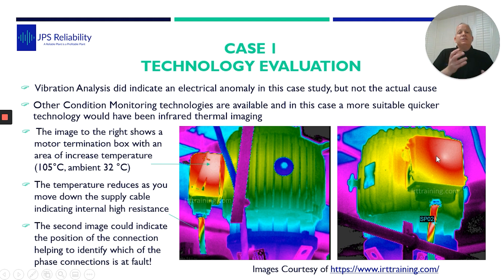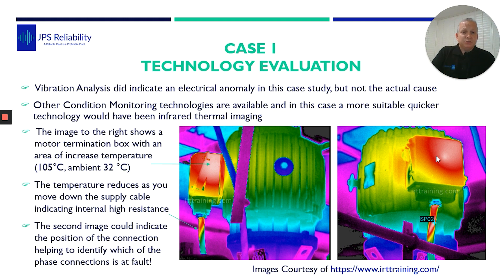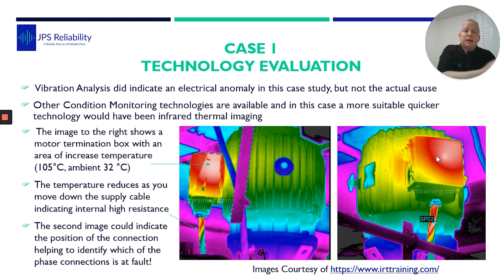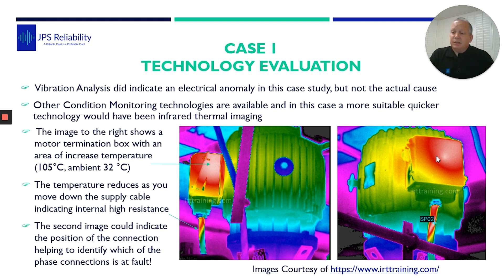So this is to say: don't just use vibration, don't just use thermography, don't just use any one technology alone. You've got to use them all together. And that's how — if I did have a thermal camera — you would have picked it up straight away. But through vibration, I did find out what was causing it.